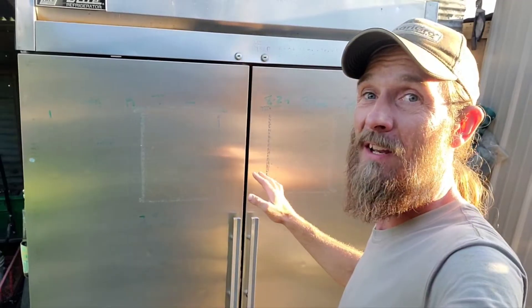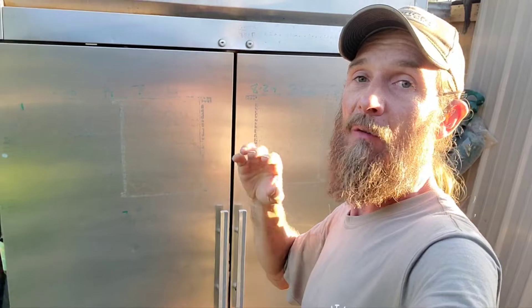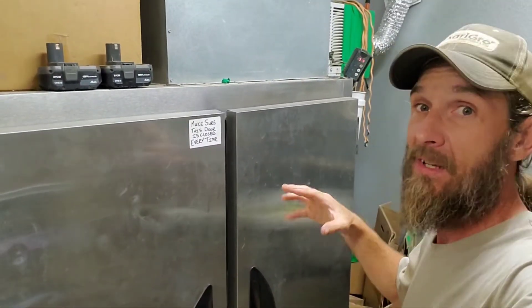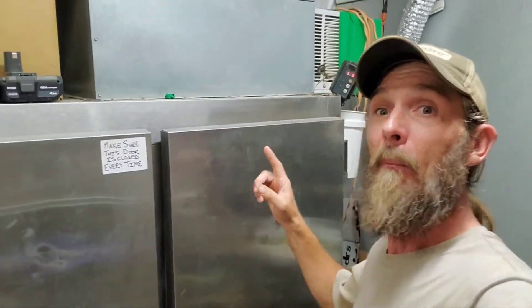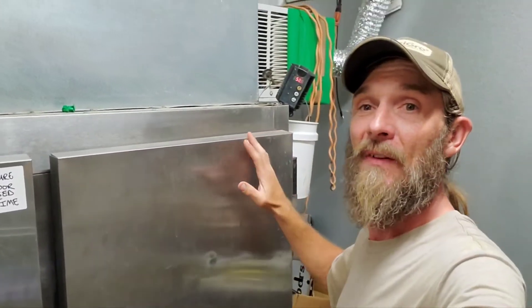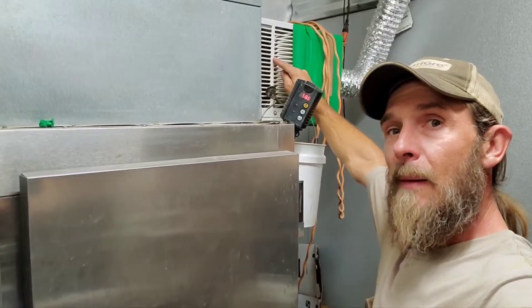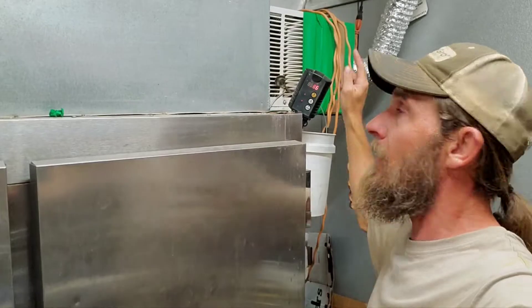Now we're going to go into the pack building to my other one that I use specifically for my fruiting crops. This unit behind me is actually the one I did years ago — the famous DIY CoolBot video. Most likely if you're watching it, you've seen it. I was much younger and less hairy back then. But this one is still up and running today with the same exact stuff. Same thing: old commercial reach-in refrigerator, $75. Used air conditioner I picked up off Marketplace, $100. Controller — these are $50.